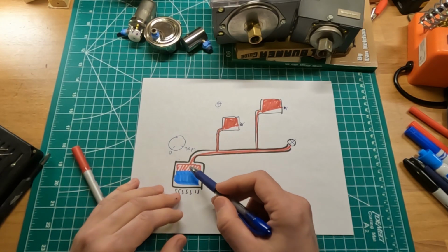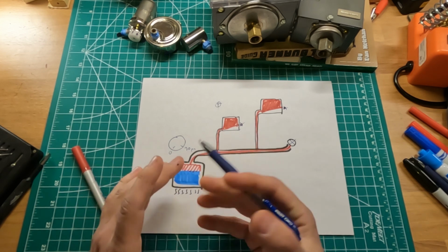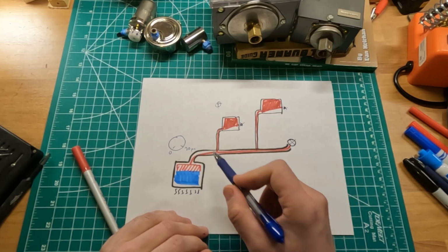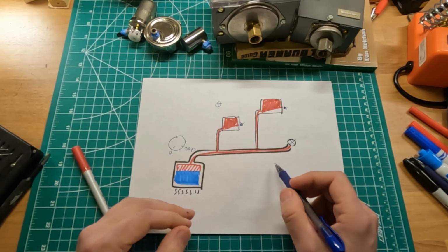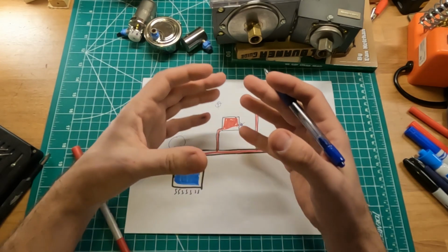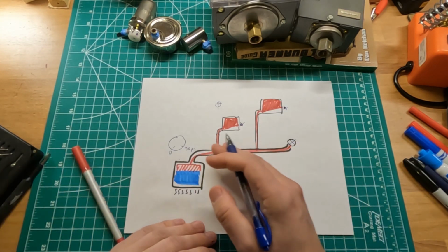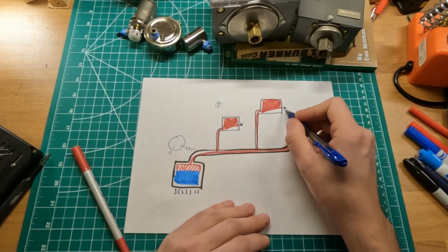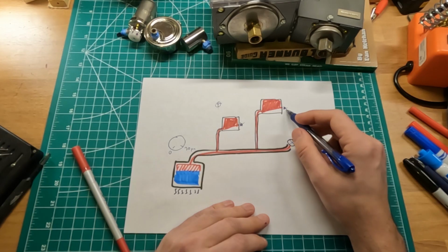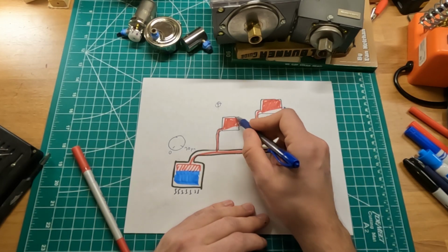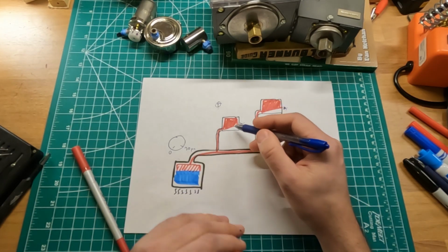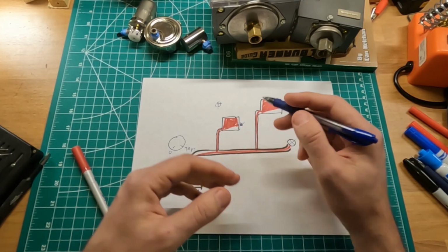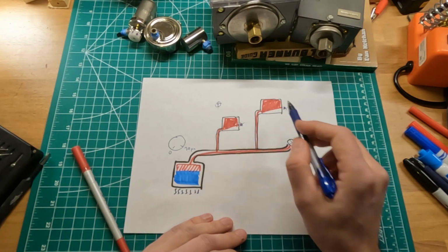But that also means that whenever pressure builds up in your system, it's in essence wasted heat. That is, the system cannot accept more steam. So in that sense, it should shut itself down and wait a little bit till the pressure goes down, till those vents open up again. Those vents are meant to open up if they cool off a bit, and that means that the steam inside the radiators condenses. So the radiators themselves can accept more heat and keep on giving off the heat to each room.